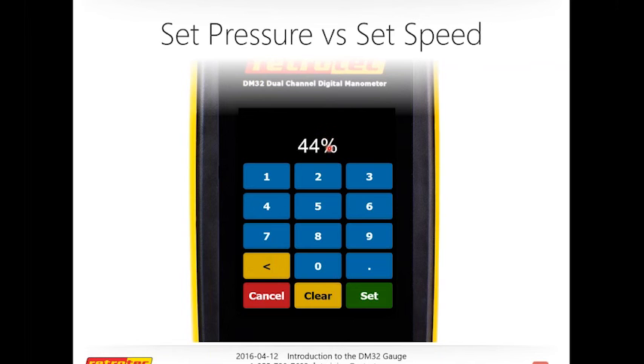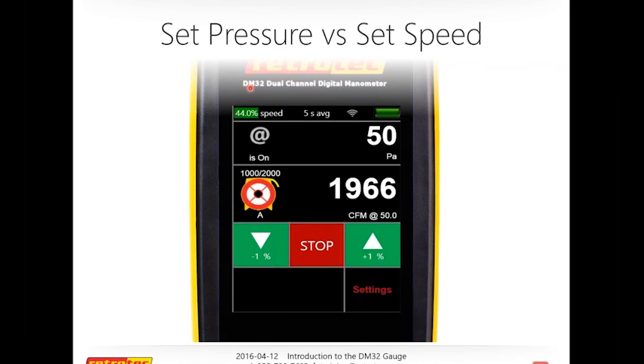So it just so happens in this example I'm at 50 pascals, but that doesn't necessarily bring you to 50 pascals. I want to explain this because people often ask me, what's the difference between setting speed and setting pressure? Well, I want to test at, say, 50 pascal. If I just set pressure and hit 50 pascal, it goes to 50 pascal. What do I care about speed? Well, here's the difference, when you use set pressure instead of set speed, like this one, set speed.